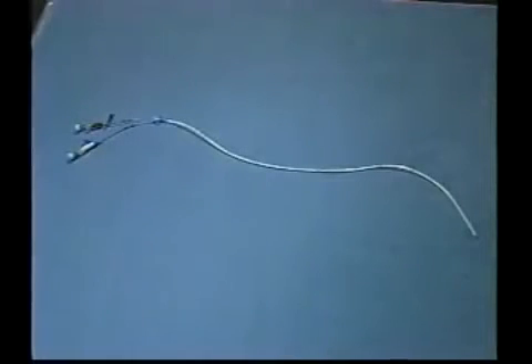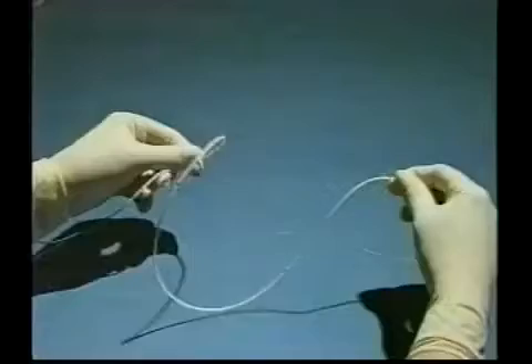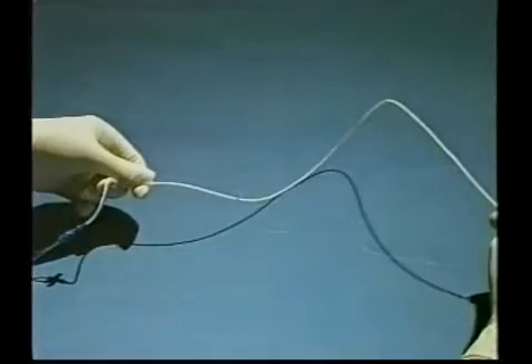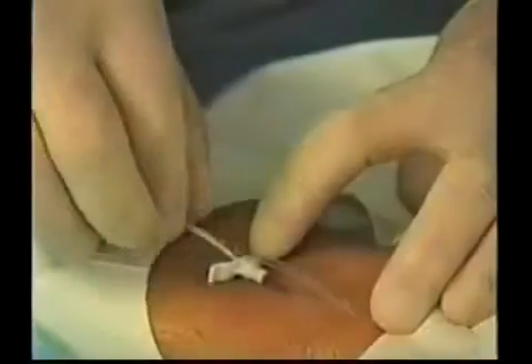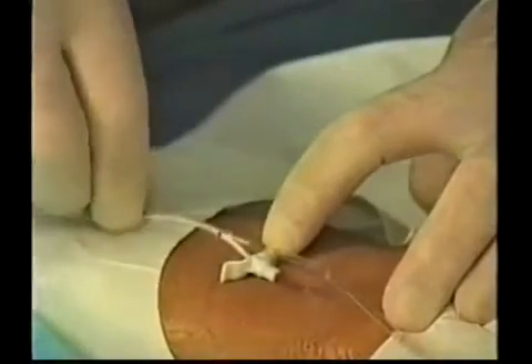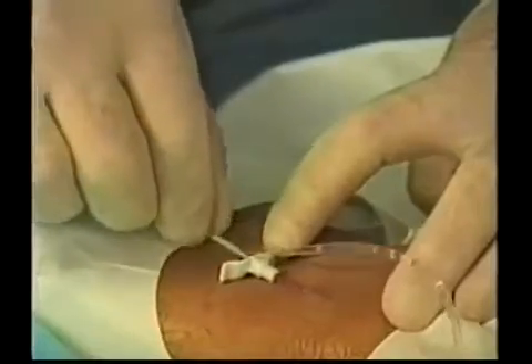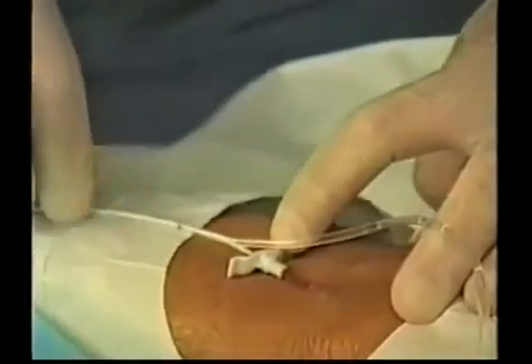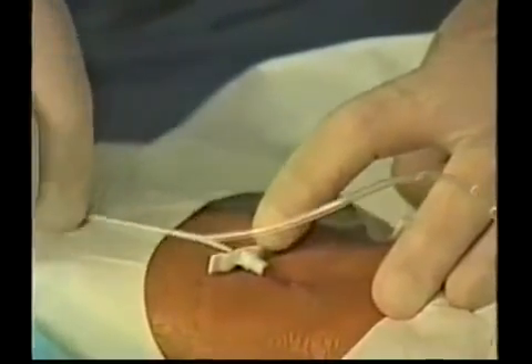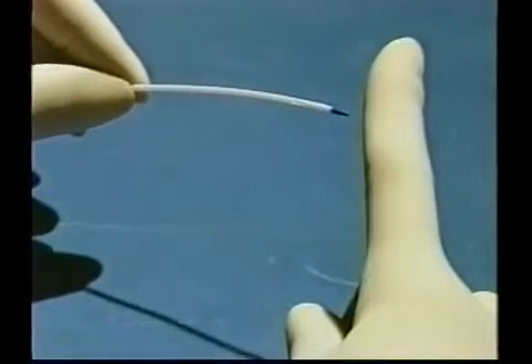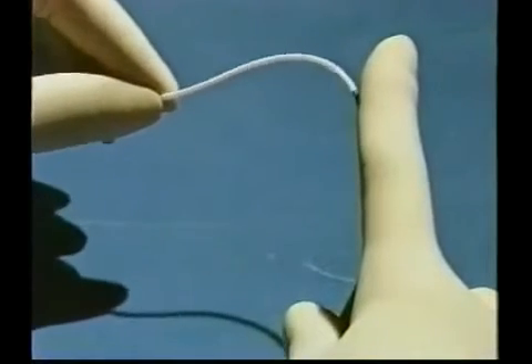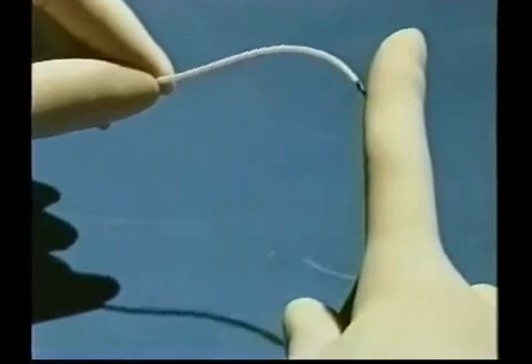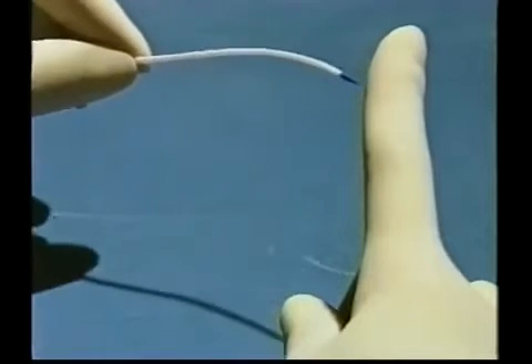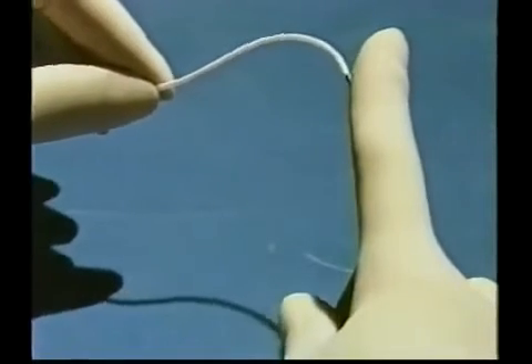Arrow's PICC catheter is constructed of polyurethane, a flexible material which softens further after insertion. Yet, Arrow's 4 French and 5 French PICC catheters have enough column strength to insert without a guide wire or stylet. The patented BlueFlex tip is a softer form of polyurethane than the body of the catheter, thereby reducing the potential for vessel wall trauma.